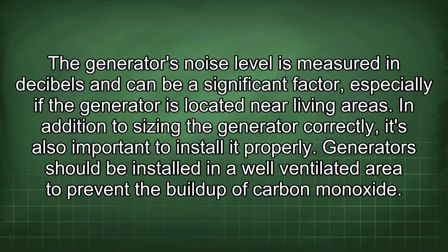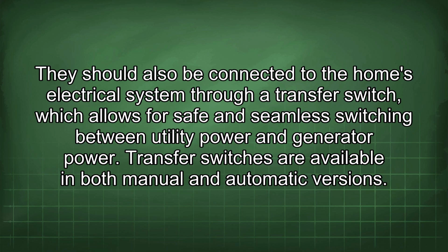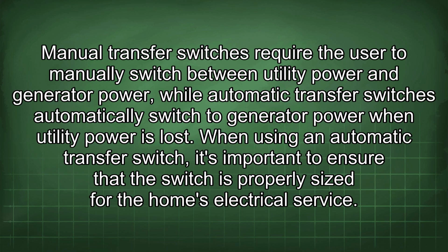near living areas. In addition to sizing the generator correctly, it's also important to install it properly. Generators should be installed in a well-ventilated area to prevent the buildup of carbon monoxide. They should also be connected to the home's electrical system through a transfer switch, which allows for safe and seamless switching between utility power and generator power. Transfer switches are available in both manual and automatic versions. Manual transfer switches require the user to manually switch between utility power and generator power, while automatic transfer switches automatically switch to generator power when utility power is lost.